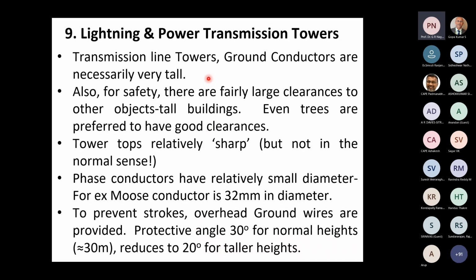Now, remember, transmission line towers and overhead ground conductors of transmission lines, transmission towers are necessarily very tall. They're metallic and for safety, there are large clearances around them so that it may behave like a tall object in the open area. Also, the tower top is relatively sharp, not in the normal sense. It's not conical sharp, but it's a very small area. For example, maybe 6 inches by 12 inches, whereas the tower bottom would be several meters by several meters. In that sense, it's a sharp top. Therefore, it's highly attractive for lightning stroke to occur.